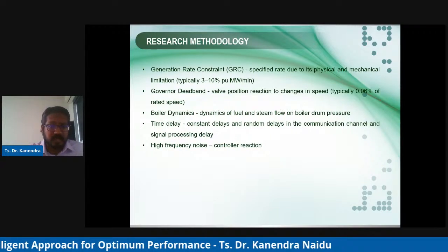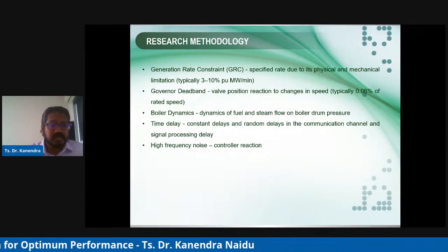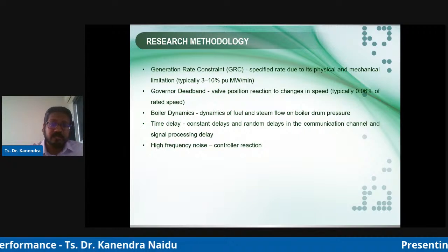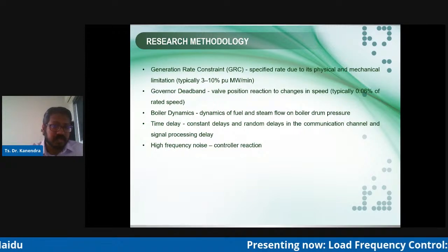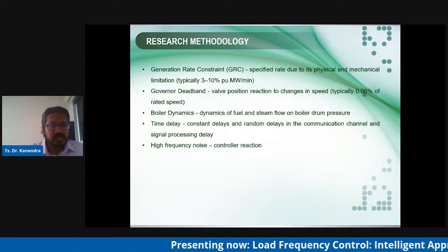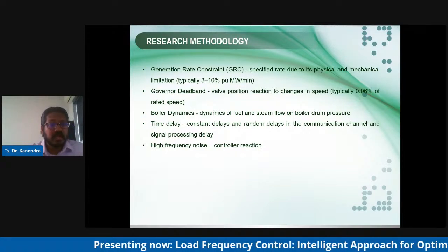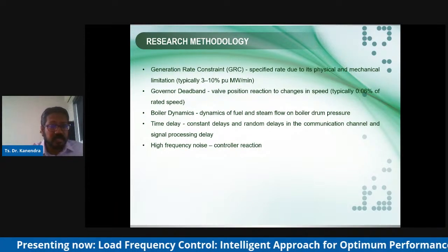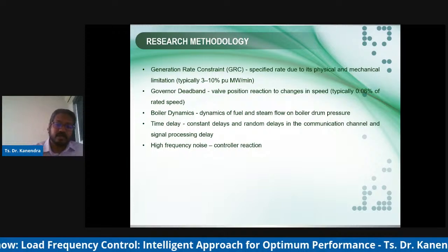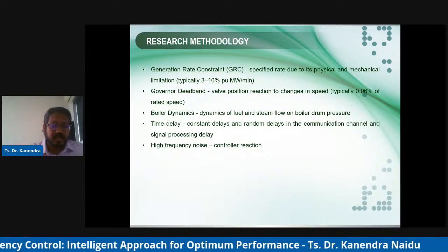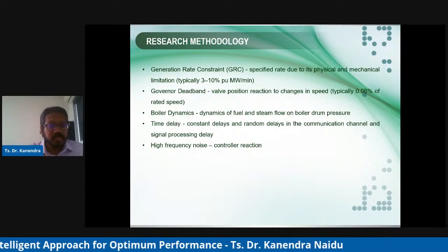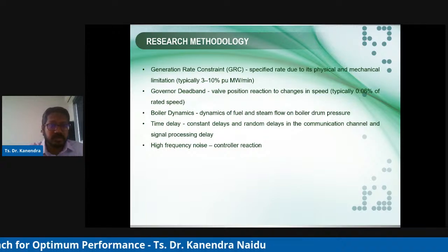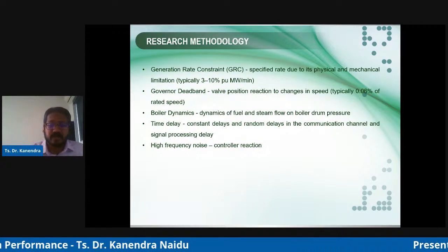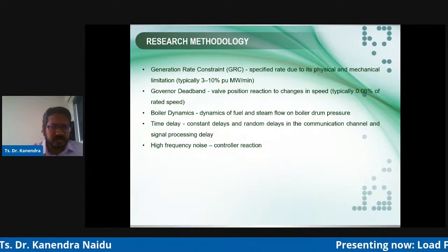And governor deadband: there are certain positions for the valve where the governor doesn't actually react to changes in speed. Also the boiler dynamics — you have a boiler in the system — and time delay. Sometimes there will be delay in propagating the information to the controller. They have delay up to 2 seconds.